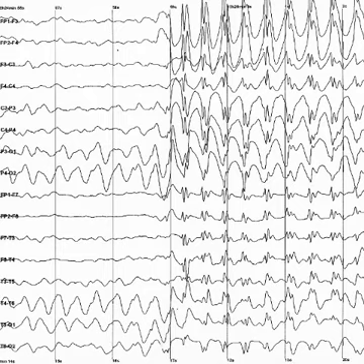Dry electrode signals depend upon mechanical contact. Therefore, it can be difficult getting a usable signal because of impedance between the skin and the electrode. Some EEG systems attempt to circumvent this issue by applying a saline solution. Others have a semi-dry nature and release small amounts of the gel upon contact with the scalp. Another solution uses spring-loaded pin setups. These may be uncomfortable. They may also be dangerous if they were used in a situation where a patient could bump their head since they could become lodged after an impact trauma incident. ARL also developed a visualization tool, Customizable Lighting Interface for the visualization of EEGs or CLIVE, which showed how well two brains are synchronized.